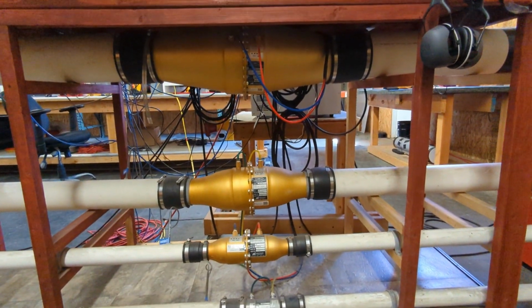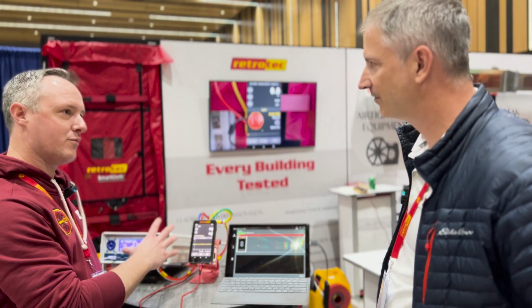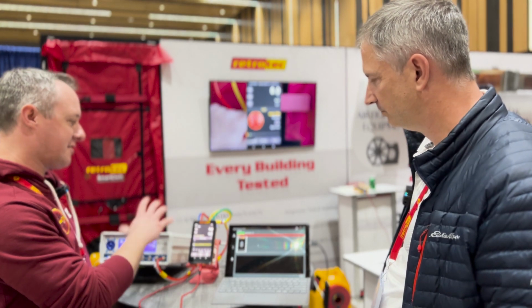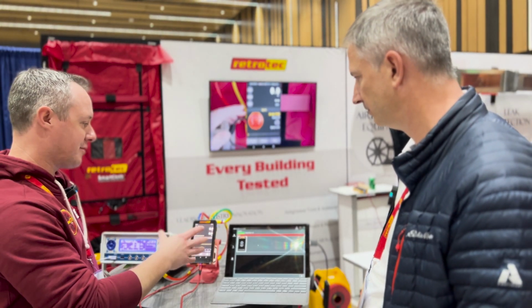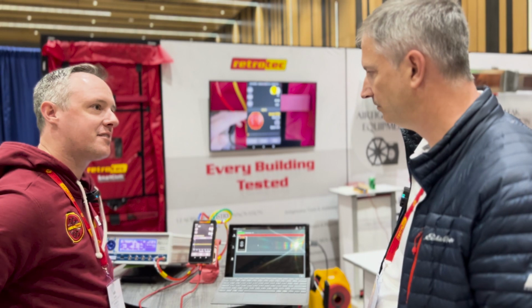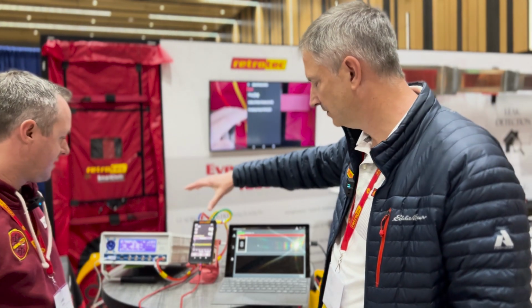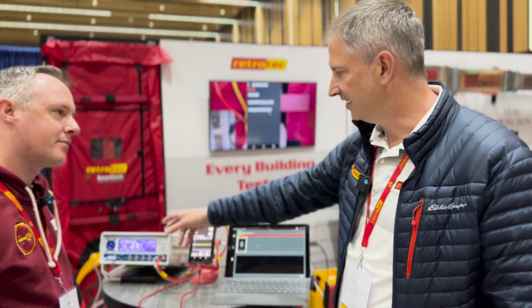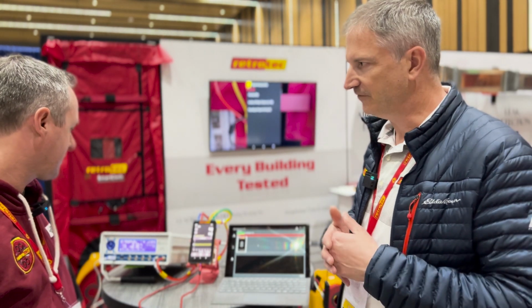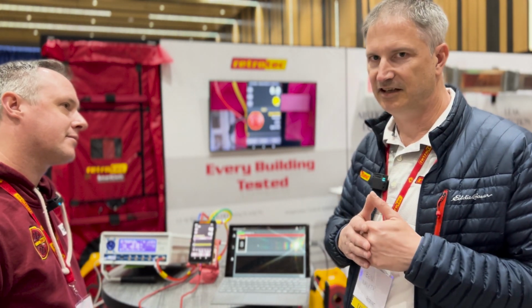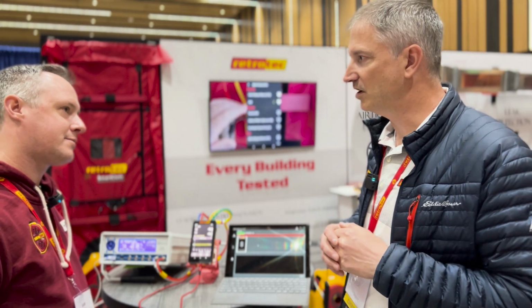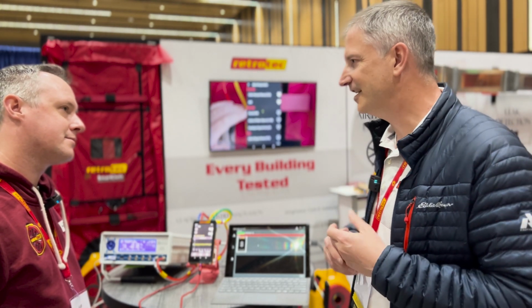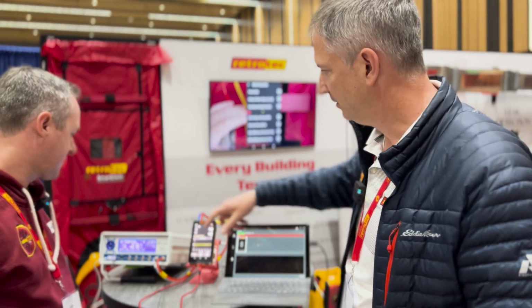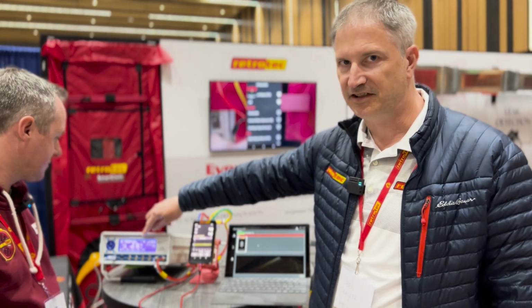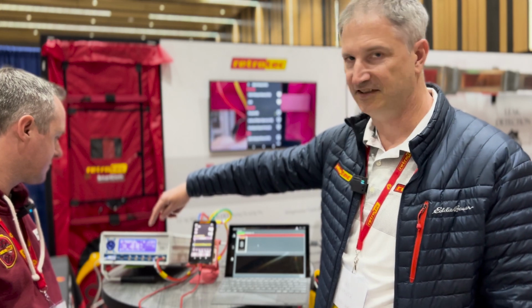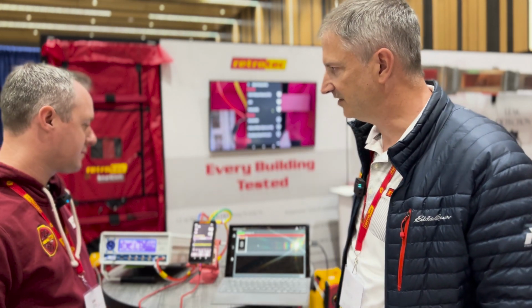Yeah. So as we have our manometer hooked up to this device, what's actually taking place? Like what is this device actually doing to our gauge, and if something's out of whack, how do we adjust it back into place? Oh, sure. So there is a linear actuator inside this that generates pressure on its own, so it can generate between 0.1 pascals all the way up to 10 inches of water, 2,495 pascals, and then it will just compare the pressure reading from its own internal pressure sensor, which is a high resolution pressure sensor, to the pressure readings that you get on the gauge.